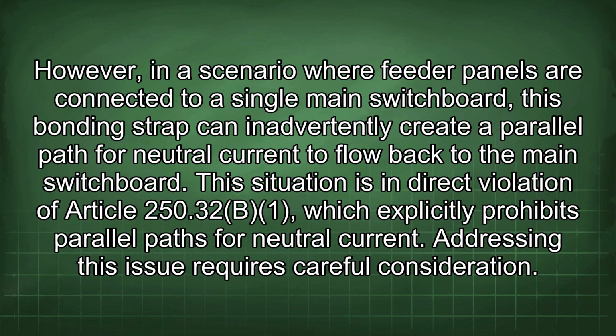However, in a scenario where feeder panels are connected to a single main switchboard, this bonding strap can inadvertently create a parallel path for neutral current to flow back to the main switchboard. This situation is in direct violation of Article 250.32, which explicitly prohibits parallel paths for neutral current. Addressing this issue requires careful consideration.